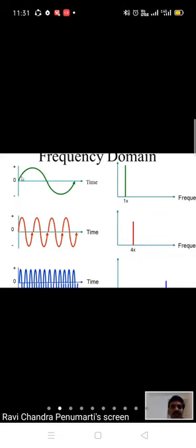So my heavy spot is giving 1x. 1x is nothing but RPM. So you will denote RPM here in terms of x. So if I am getting a 1x frequency, there is some heavy spot on the shaft. If I am getting a 4x frequency, it says my fan blades are not proper. If I am getting 12x, my gear teeth are not proper.